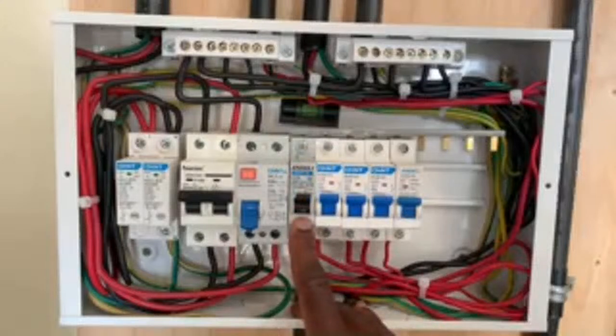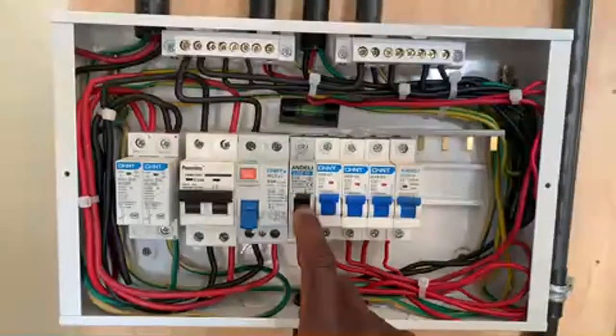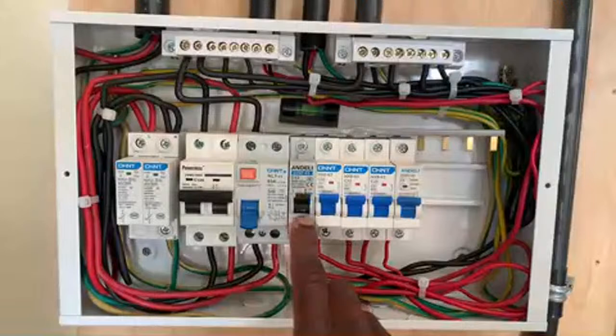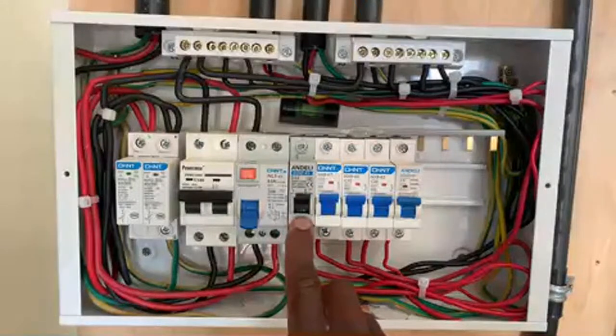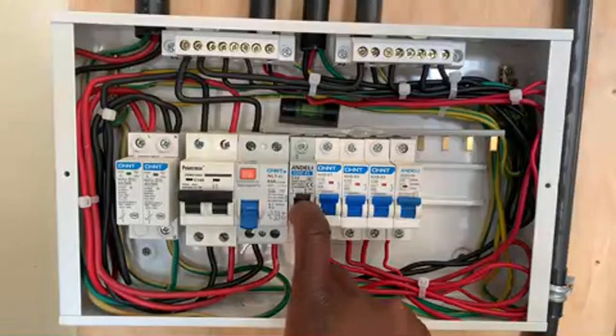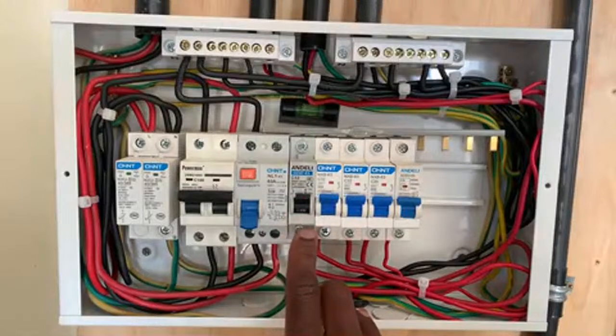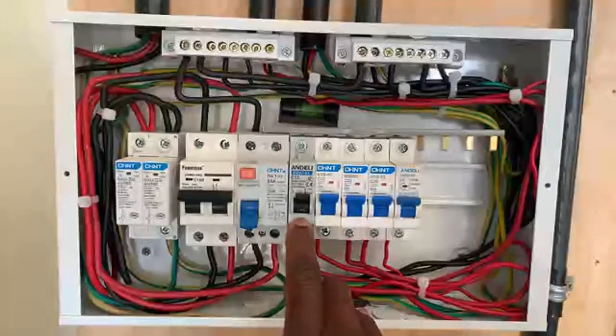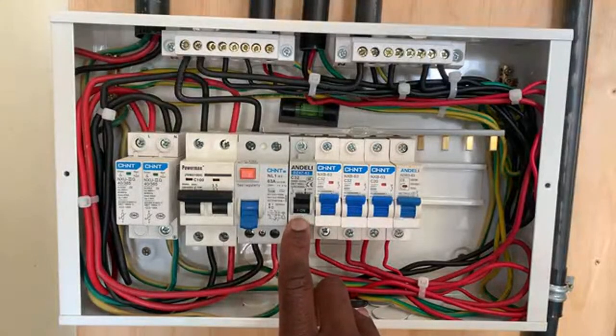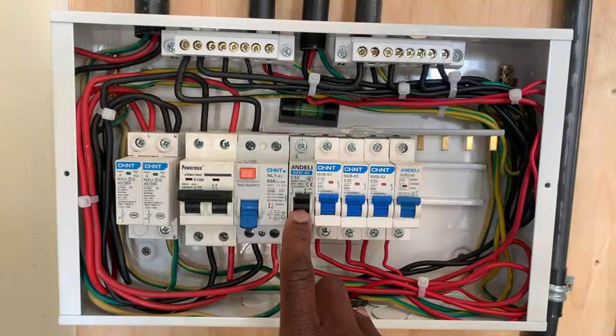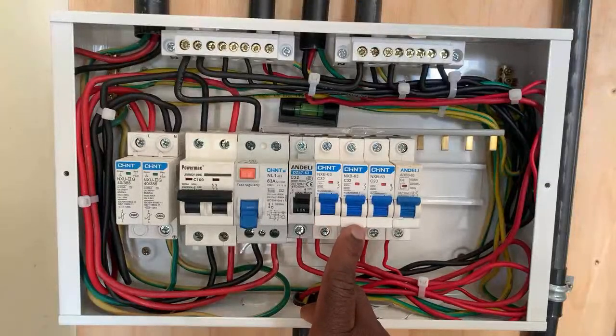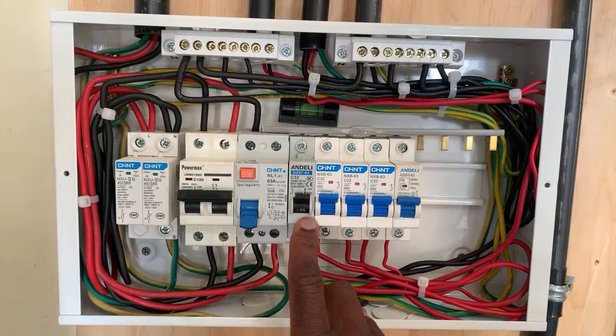Direct connections, I don't know if I should talk about that, because when you connect directly here and you evade this circuit breaker for one or two reasons best known to yourself, that is a recipe for disaster, as we normally say here at Top Heights Electricals and Electricians. Why? Because heaters, in most cases, have a lot of issues. Either they are drawing a lot of current, or there is a short circuit, or there is an issue of water coming in contact with the phase and the neutral, which is also another form of short circuit in that appliance. If this is not a quality one, or if you have connected an MCB that is not quality in handling that current, then definitely there will be an issue in case it is supposed to trip and it doesn't trip.